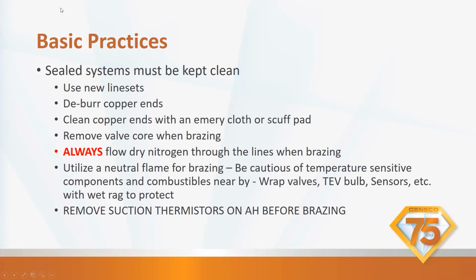Sealed systems must be kept clean. You must use new line sets, deburr the copper ends, and clean the copper ends with emery cloth or a scuff pad before you braze. Remove the valve core when you're brazing. If you don't remove the valve core, you're actually fuming rubber into your system off of the O-rings on your valve cores.